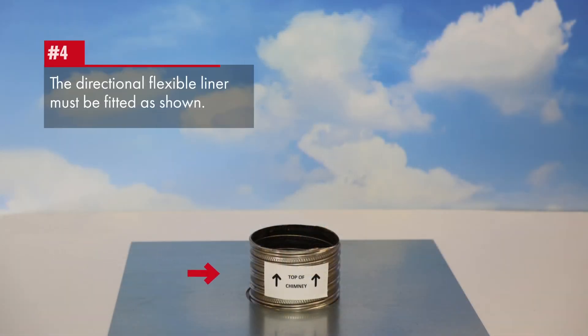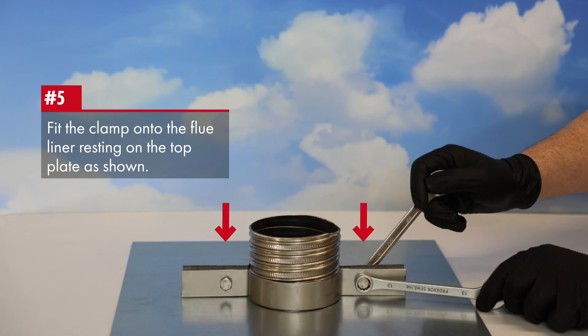The flue is directional and must be fitted as shown. The clamp is fitted onto the flue to take the weight of the liner and rests on the top plate.